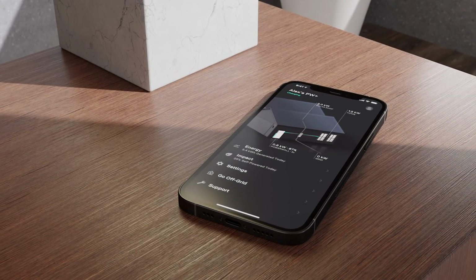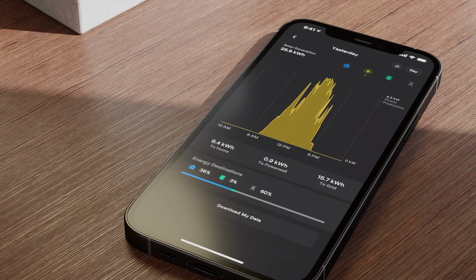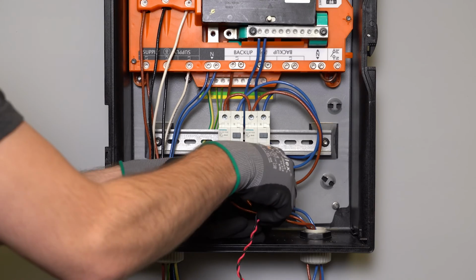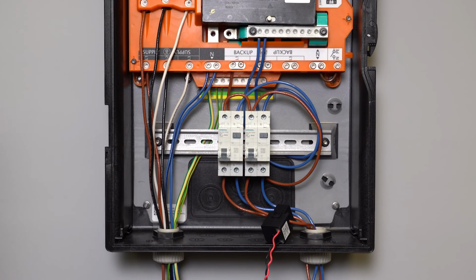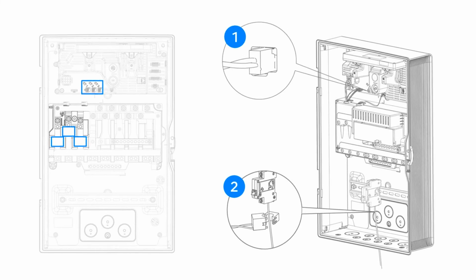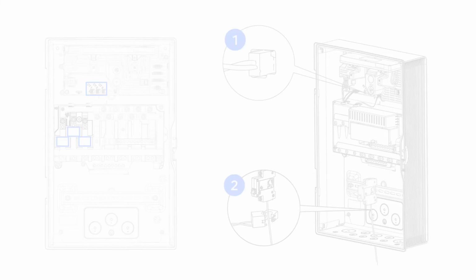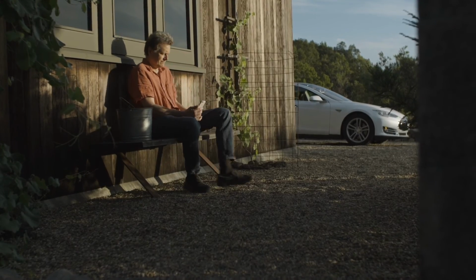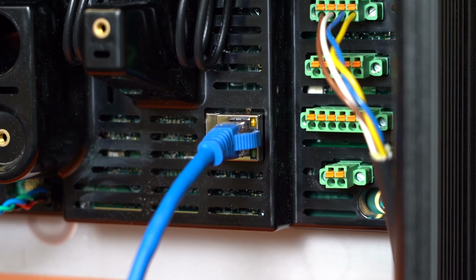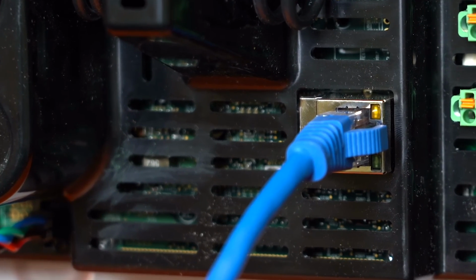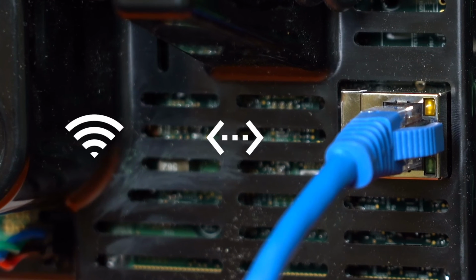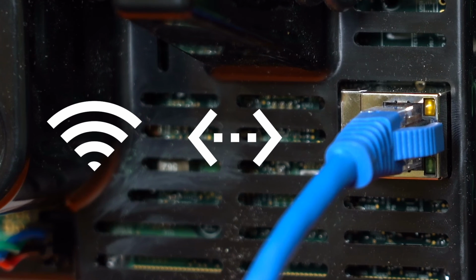Visibility on power and energy data is needed for Powerwall systems to operate properly. As mentioned earlier, metering is covered in a separate video. Please review the video and consult the installation manual for details. Reliable internet connectivity is important. For best performance, connect Ethernet with a Cat5 or higher cable as to not rely solely on Wi-Fi. The gateway will automatically select the network option with the best connection.